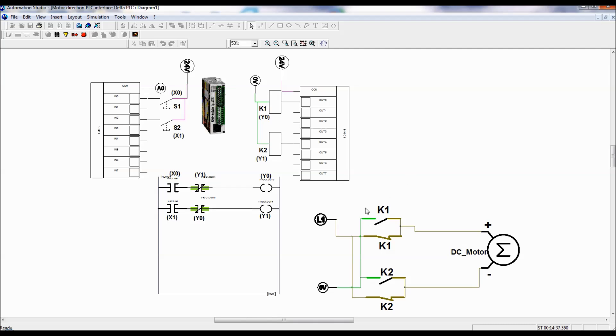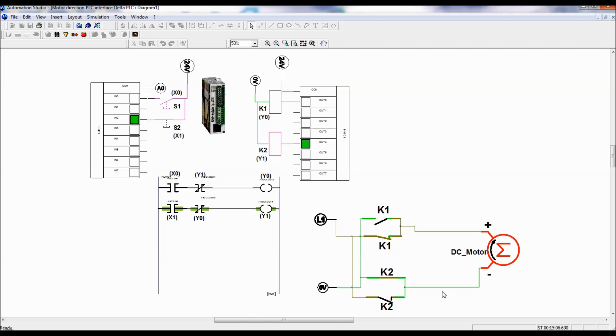Look at this wiring diagram. I will press S1 switch — assume that is forward. If you press S1, the motor turns clockwise. You can see the plus is on the green line, meaning positive here and negative there — so it runs clockwise. If I release S1 and press S2, the positive line shifts, so the motor rotates in reverse direction — K2 relay is on. Checking interlocking: motor is rotating in reverse, but if you give a command for forward, it will not work. Y0 is not getting on, K1 relay is not getting on. This is how interlocking prevents both relays from switching on simultaneously.